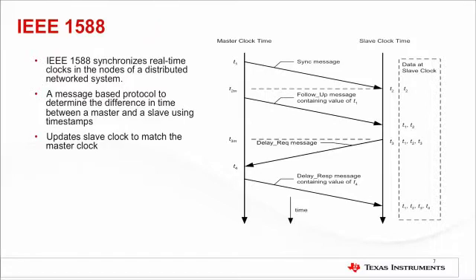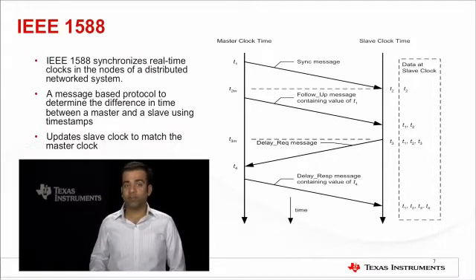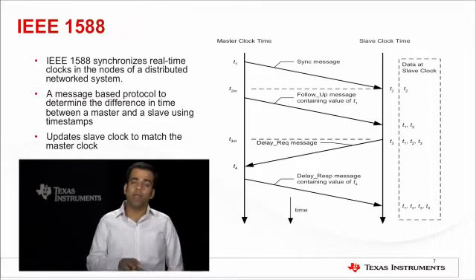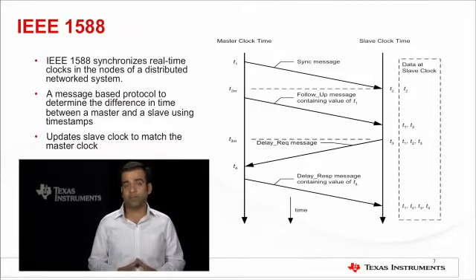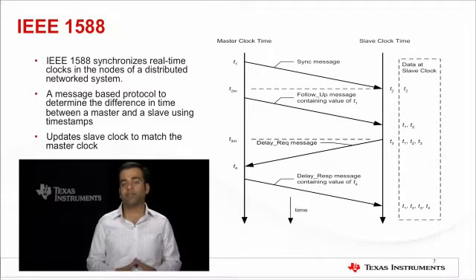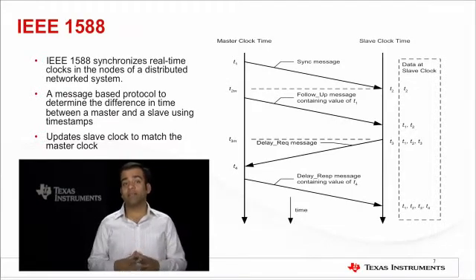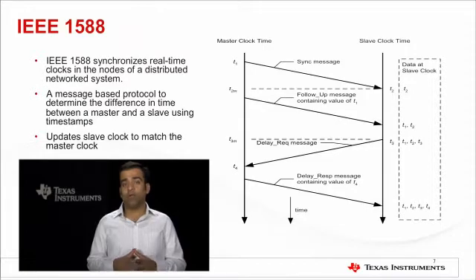Now it's time to take a quick look at the IEEE 1588 standard. IEEE 1588 is a protocol that allows clocks on different devices in the network to be set at the same time. This is essential for precise control and measurement of automated manufacturing and test equipment where it is cost-prohibitive to use GPS receivers, or simply where GPS signals are not available for synchronization. The protocol works by exchanging timestamped messages between nodes and uses the delay determined by these timestamps to update the device clock. This update occurs on a regular basis, and the precision of the system is set by the amount of error induced into the timestamps. This error can be reduced by capturing the timestamp closer to the wire. This standard replaces expensive coaxial timing cables for Ethernet-based control and measurement systems. It does not define how the clock is updated or how the timestamps are captured — these are subject to the system implementation. Hardware assist at the PHY level can provide both of these operations.